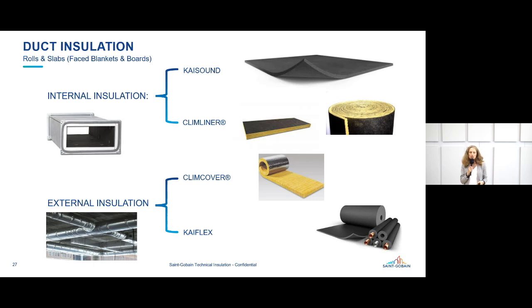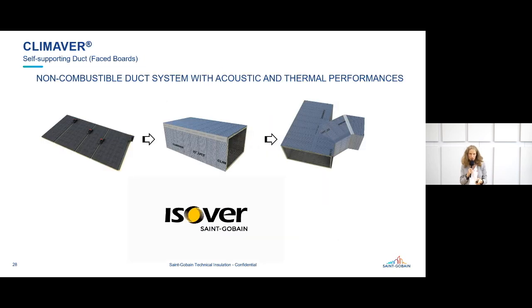If we now focus on ducts, there are three types of insulation that you can have. The first one is that you can put some open porosity insulation material on the internal face of your metal duct. This could be Kaisound or Climliner. When you put open porosity insulation material in a duct, you will have both sound attenuation and sound absorption. On the other hand, if you put your insulation material outside of the metallic duct, then you will only reach sound insulation, because in this case you will only have the mass and spring system. You will not have the absorption through the material. And there is a third solution, which will be explained by Guillermo.